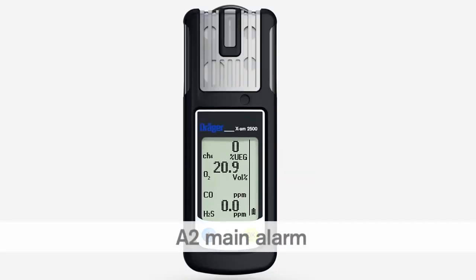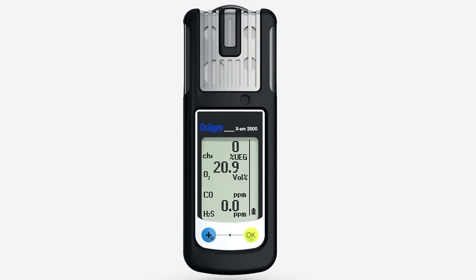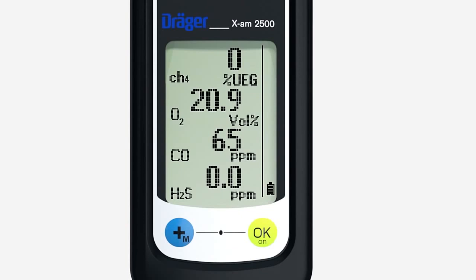If this alarm is activated, leave the danger area immediately. The A2 main alarm signals danger of death. An audible double tone sounds. The visual and vibration alarms are periodically repeated. A2 is shown in the display. An A2 main alarm cannot be acknowledged.